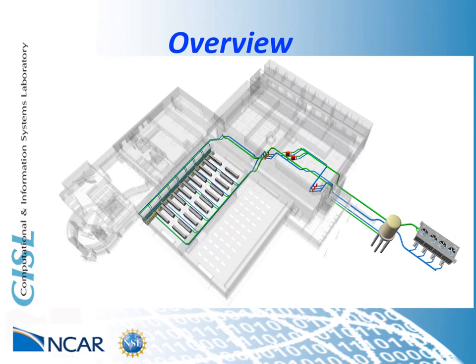This slide is a quick overview of the footprint of the NWSC with the cooling tower, water tank, and cooling distribution system layout. The water tank is a 60-foot tall tank containing 135,000 gallons of water with a nitrogen blanket atop the water line. The NWSC design has 2 modules, A and B. Module A was built out as shell space initially, and we are currently in the process of occupying Module A. This design feature puts Module A and Module B a decade apart so as to stagger the age of the infrastructure components between the 2 modules.